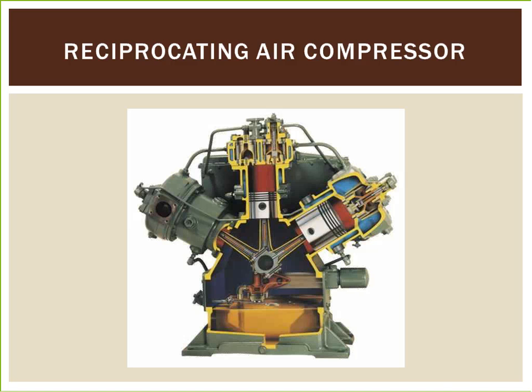The reciprocating air compressor is single acting when the compressing is accomplished using only one side of the piston. A compressor using both sides of the piston is considered double acting. Load reduction is achieved by unloading individual cylinders. Typically, this is accomplished by throttling the suction pressure to the cylinder or bypassing air either within or outside the compressor. Capacity control is achieved by varying speed in engine-driven units through fuel flow control.